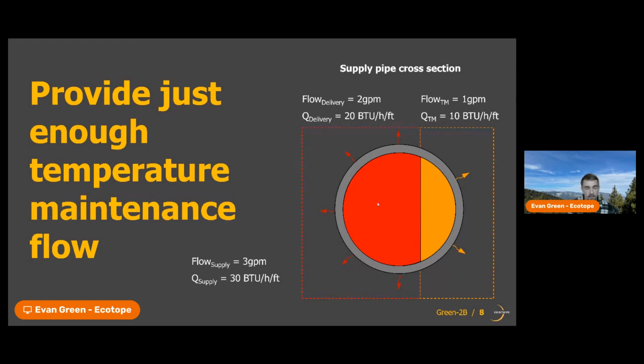And so maybe they're supplied at 120, but they're losing heat at the same rate. And so the heat loss associated with each of these flows is going to be proportional to the percentage of the pipe that each flow makes up. So if we assign some numbers to that, if we're flowing 2 GPM out to a fixture or a set of fixtures, and we need to accompany that with 1 GPM of temperature maintenance flow just to keep it flowing high enough, and we have 30 BTUs total, we're going to have this delivery heat loss of 20 BTUs and the temperature maintenance heat loss of 10 BTUs.